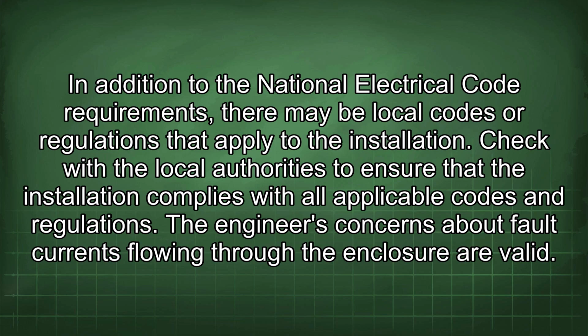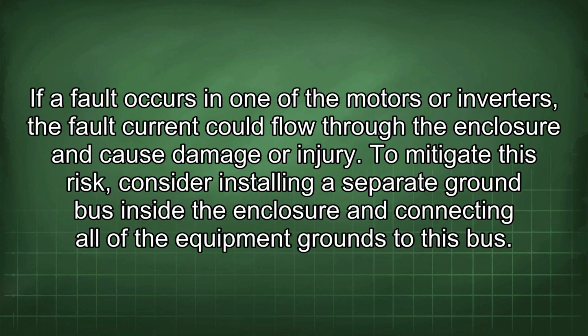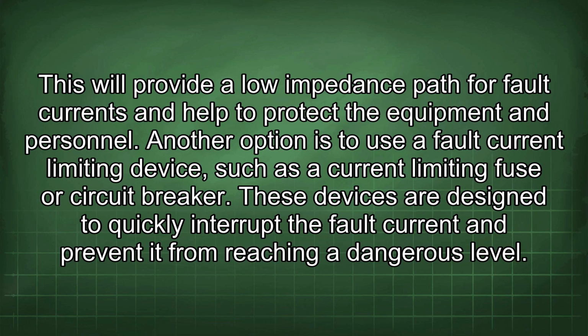The engineer's concerns about fault currents flowing through the enclosure are valid. If a fault occurs in one of the motors or inverters, the fault current could flow through the enclosure and cause damage or injury. To mitigate this risk, consider installing a separate ground bus inside the enclosure and connecting all of the equipment grounds to this bus. This will provide a low impedance path for fault currents and help to protect the equipment and personnel.